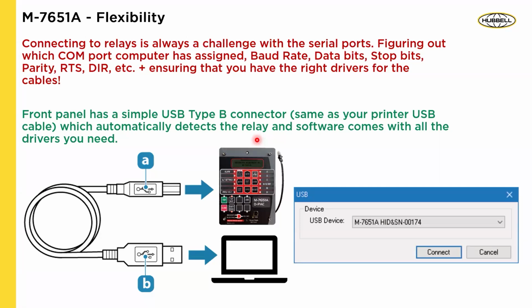So the idea there is to simplify that. It's a USB connection, it's a printer cable that connects right in the front, and it comes with all the drivers you need. So software is pre-populated with the drivers, so you don't need to go in and find out which COM port you have. If you're used to connecting to a serial port, then this will be a breeze. And when you open the software, when you try to connect, it automatically detects what USB device there is on the system and what's the serial number, so you can identify exactly which relay you're connecting to.